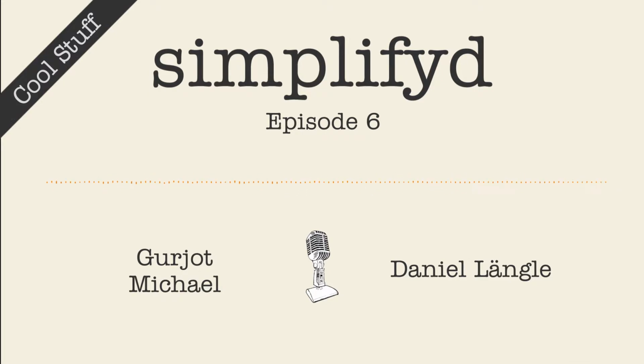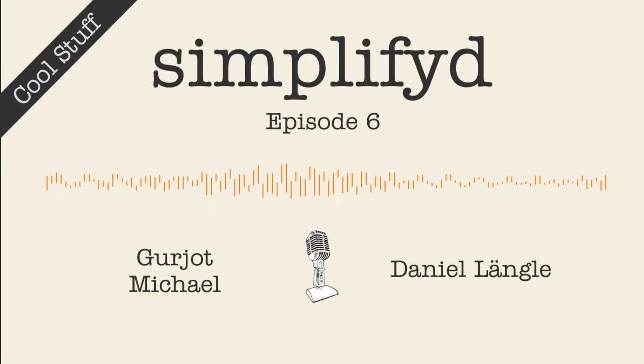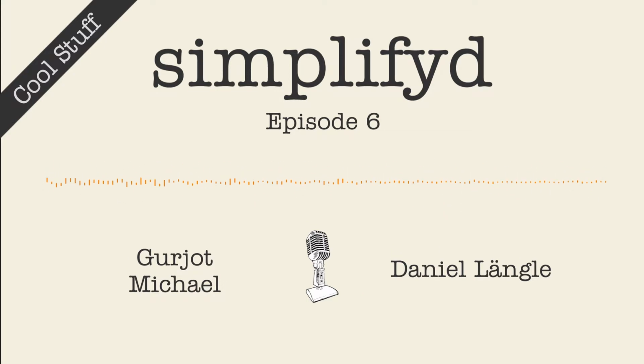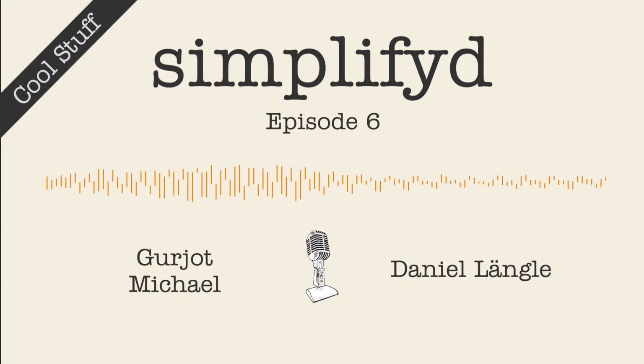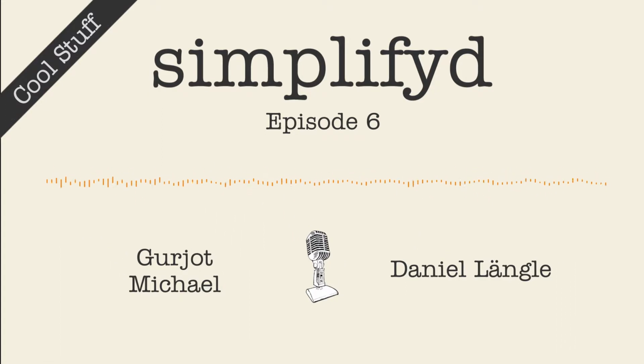Could you just tell me, what was the old technology? You said it just blindly pumped blood or whatever through to the patient. So there's no monitoring at all, or do they just kind of guess how much was going in? There is monitoring, but not of the flow, but of the pressure of the tube. So they have a pressure sensor. Right. So if something completely blocks at the end, the tube is slowly building up the pressure like a balloon. Yeah. And when a pressure limit is reached, the pump starts to beep. Yeah. But now this takes a while.